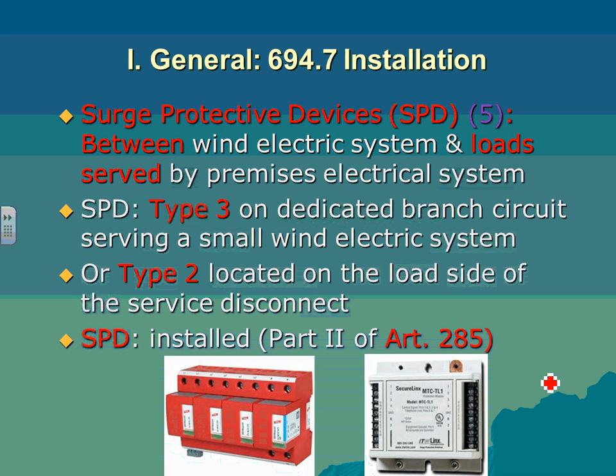It's a standard engineering requirement right now. It's not a big deal. Every project I work on, right at the main service, the 4,000 amp or the 200 amp service for commercial and industrial, not dwelling, you have to have a surge protector. So if you have a surge coming from lightning or from a high voltage hitting a low voltage line, a big jump in the voltage that could burn your equipment, it will capture that voltage and take it to Mother Earth. This is what the surge protective device's job is.